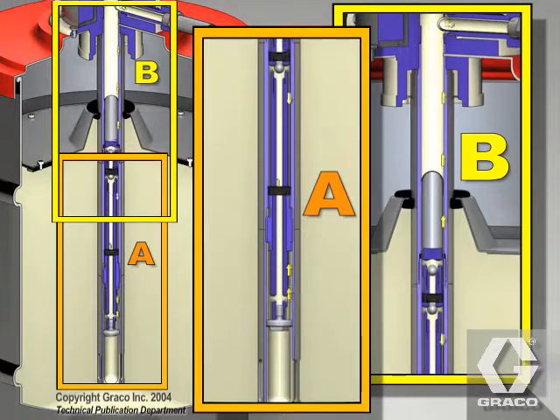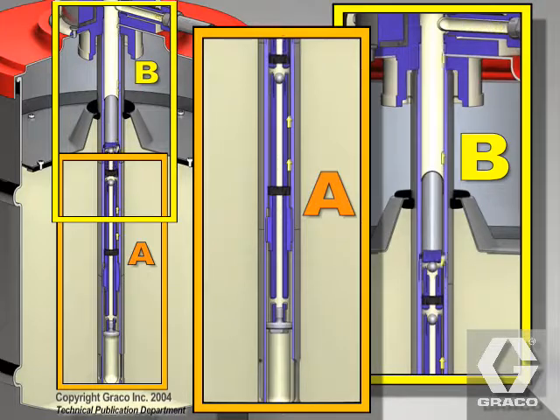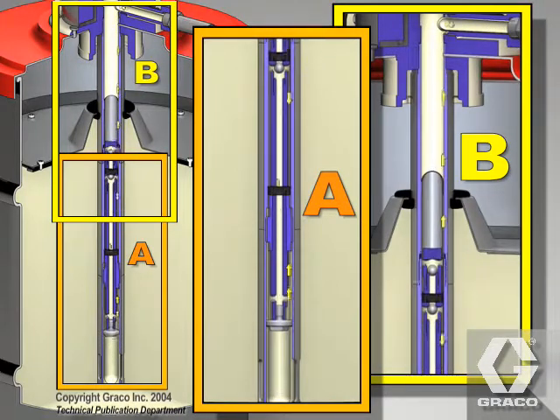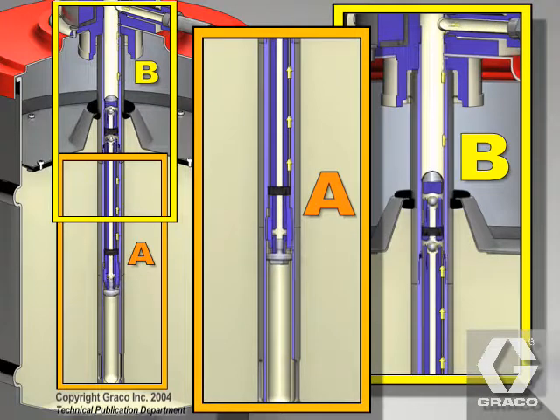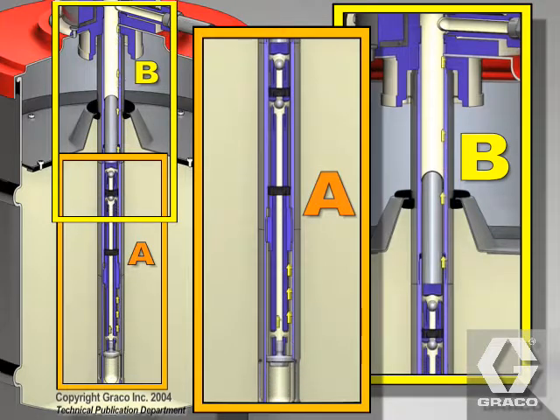On the downstroke, the priming piston at the bottom of the pump moves down into the lower pump cylinder, creating a low pressure area. As the priming piston clears the slots at the bottom of the pump, grease is pushed into the low pressure area.